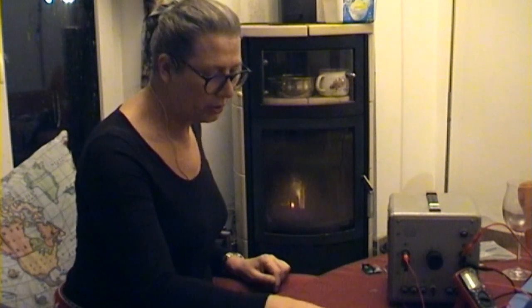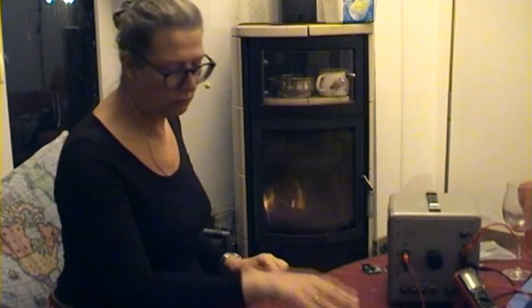If it's cold enough, it switches the solar panels back on; if it's too hot, it switches them off and cools. Then for temperatures between, I think, 35 and 9 degrees Celsius, it just switches the solar panels on if the voltage is above the battery voltage minus 1 volt or so — meaning it switches when there's no real difference between the battery and the solar panels, giving us the best switching point possible.